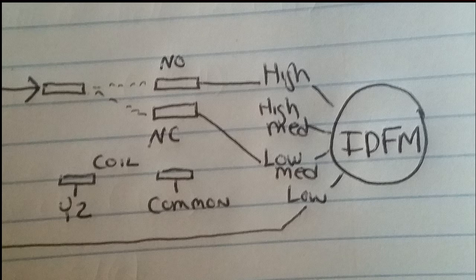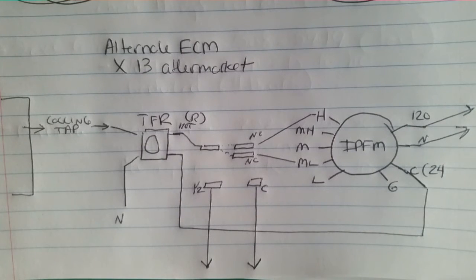And we're going to look at one alternative way to use an aftermarket X13 motor for the same purpose. As you can see, we have a similar drawing to up top. We have our relay, we have our indoor fan motor, we have our cooling tap. We kind of ignored the heating tap this time so it wouldn't be too cluttered. But as you see, we added a transformer. You see TFR as transformer. We have our cooling tap powering the transformer, the other leg going to neutral. It's 120 volts to 24 volts.